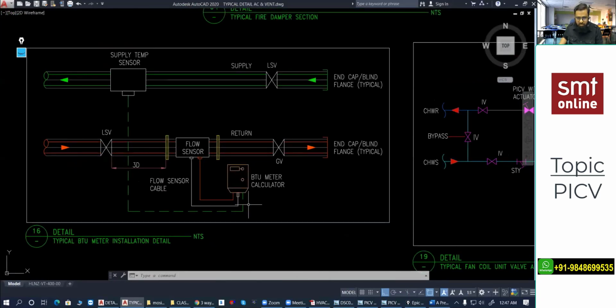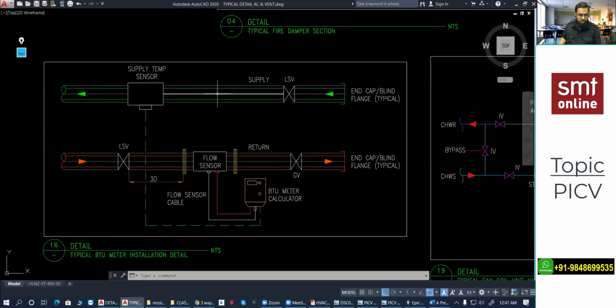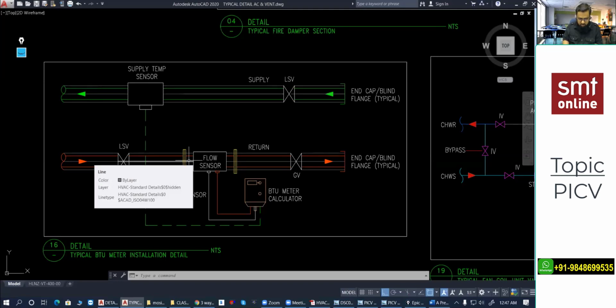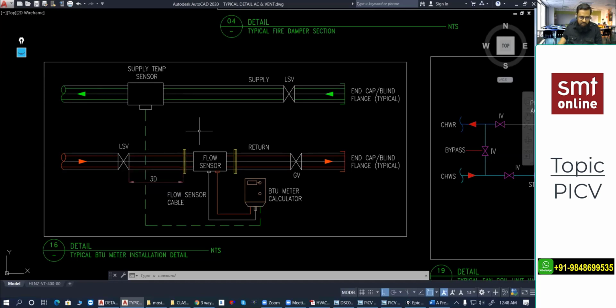Apart from this, there is one more thing which I have not covered yet, that is the BTU meter. In a district cooling system, you'll find this BTU meter. Here you see the supply to the AHU and the return from the AHU or FCU. For example, in a multi-floor residential building with different flats, for one flat we require one BTU meter, or for one villa, one BTU meter. Here you can find the position, and this temperature sensor is nothing but a thermowell.